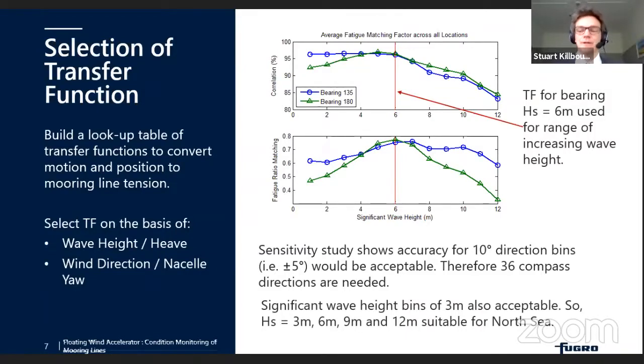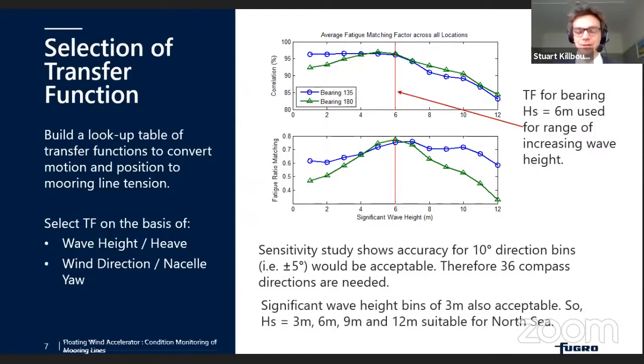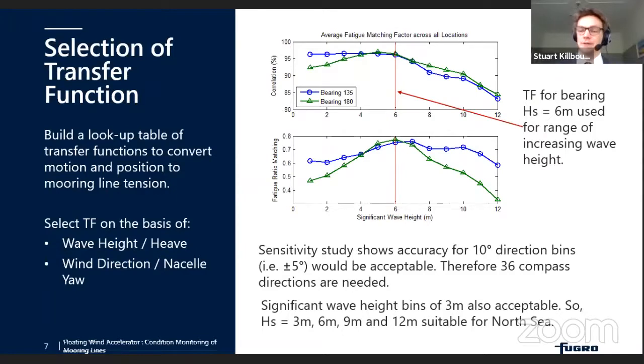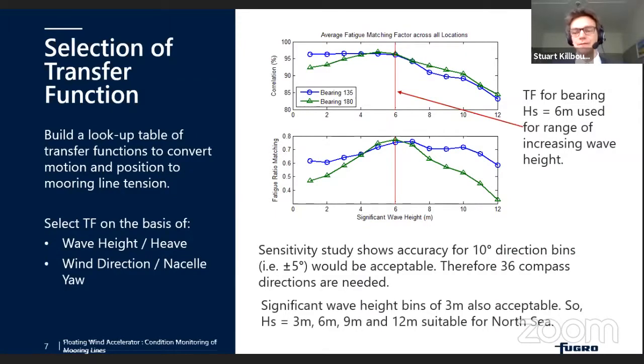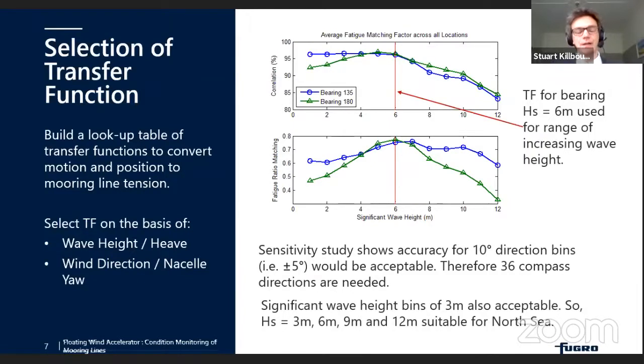In practice, the monitoring system needs to determine wave height and wave direction. These can be measured directly with wave height instruments and wave radars, or we can use proxies: the heave motion of the floating hull, which we would measure anyway, and the nacelle yaw — where the turbine rotates to face the wind — which is output by the control systems and gives us wind direction.